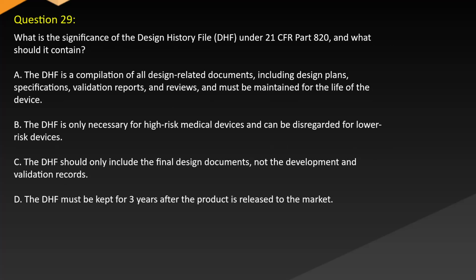Question 29. What is the significance of the Design History File (DHF) under 21 CFR Part 820, and what should it contain? A. The DHF is a compilation of all design-related documents, including design plans, specifications, validation reports, and reviews, and must be maintained for the life of the device. B. The DHF is only necessary for high-risk medical devices and can be disregarded for low-risk devices. C. The DHF should only include the final design documents, not the development and validation records. D. The DHF must be kept for 3 years after the product is released to the market.